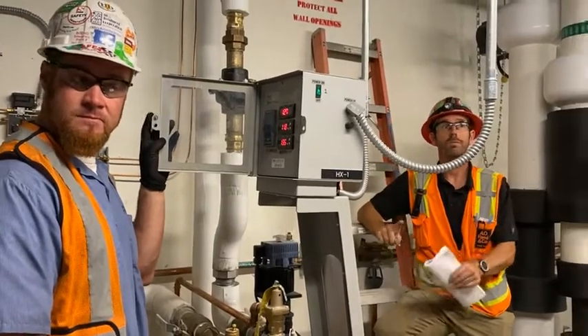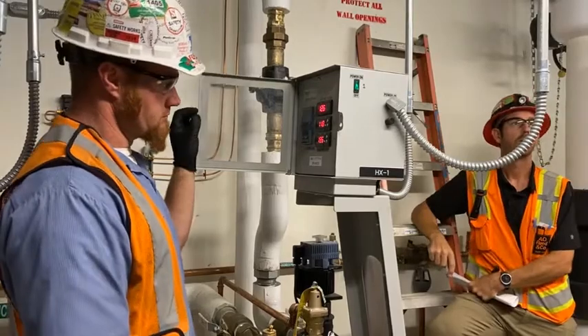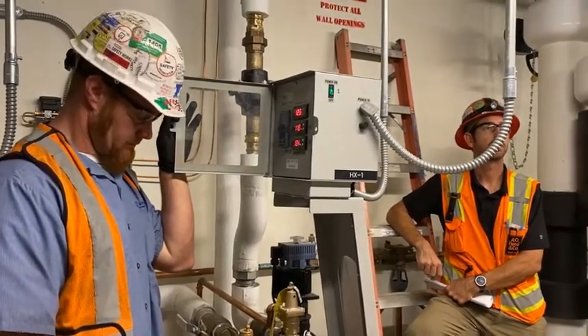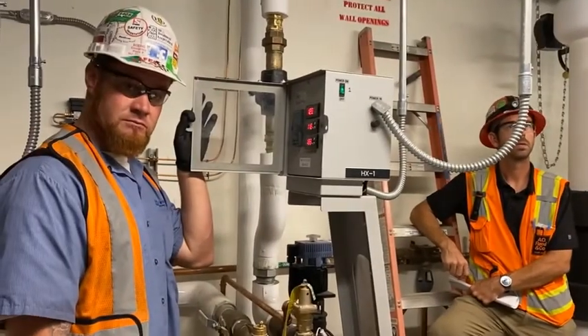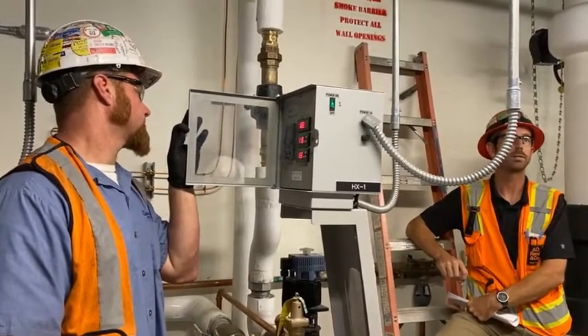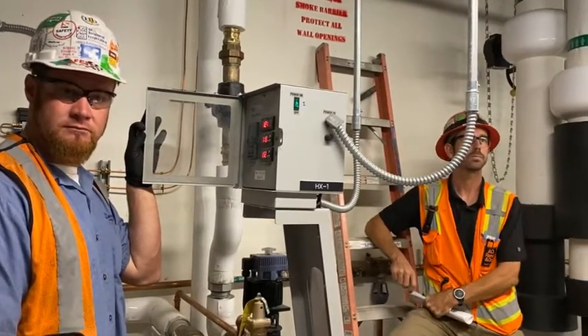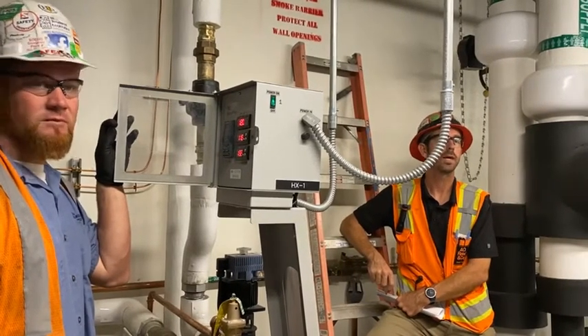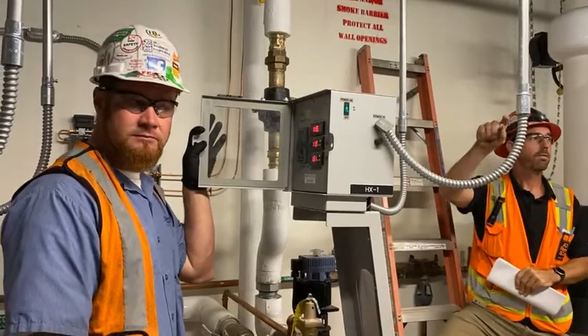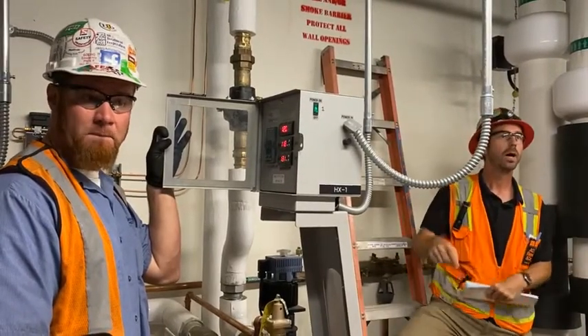The highest demands of the building will require both heat exchangers on at the same time. Then it goes to the mixing valve. The heat exchanger is only putting water into the tanks — from the tanks it goes at 140°F and then the mixing valve brings it to 120°F leaving to the fixtures. On the eighth floor when you open the hot water faucet you should read around 120°F — there may be about five degrees of thermal loss. If we get 100°F on the eighth floor, that's a problem — we're definitely not circulating.